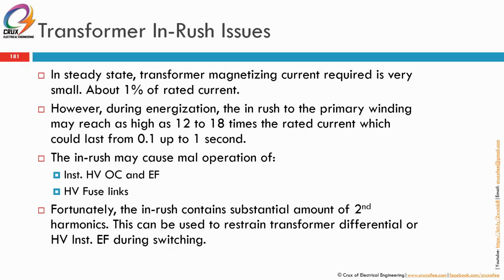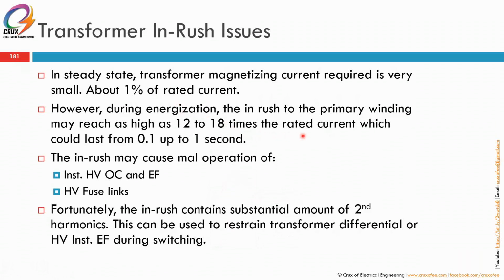So transformer inrush, so selalu berlaku bila first time you nak energize transformer lah. Every time you nak energize lah sebenarnya. In steady state, transformer magnetizing current required is very small lah, about 1% of the rated current. However, during energization, the inrush to the primary winding may reach as high as 12 to 18 times of the rated current, which could last from 0.1 up to 1 second. Pernah juga kita jumpa yang sampai 2-3 saat pun tak turun-turun lagi dia punya inrush.